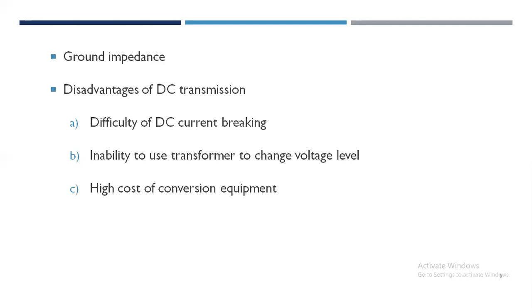Let's see the disadvantages of DC transmission. First is difficulty of breaking DC currents, which results in high cost of DC breakers. Second, inability to use transformers to change voltage levels. Third, high cost of conversion equipment. Fourth, generation of harmonics which require AC and DC filters, adding to cost of converter stations. Next one, complexity of control.